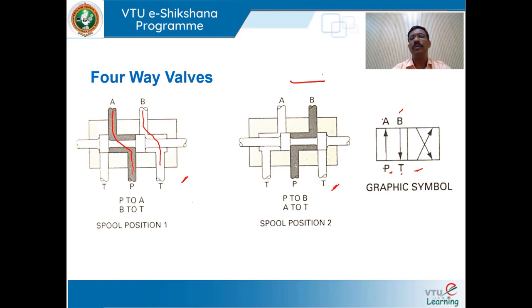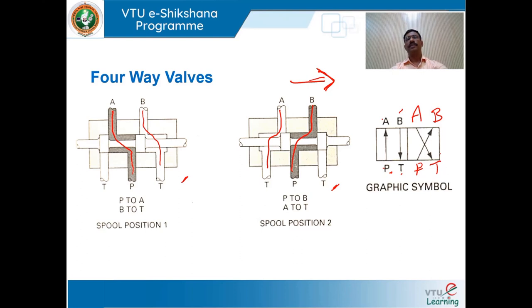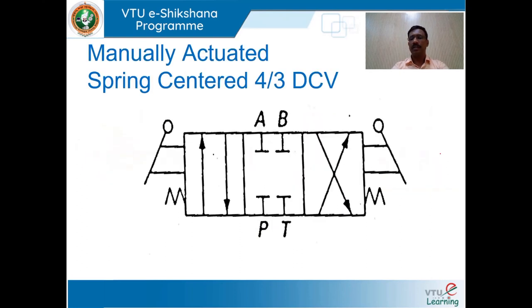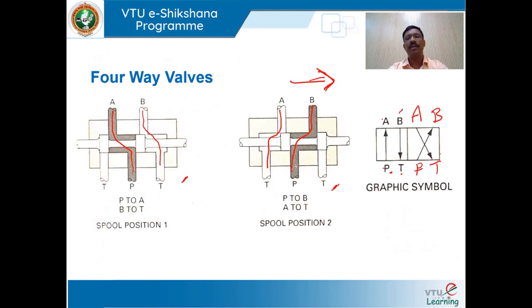When the spool slides within the valve body and moves to the second switching position, P is connected with B and A is connected with T. This is how a four-way valve works. A three-way two-position valve is used to control a single acting cylinder, and a four-way two-position valve is used to control double acting cylinders.